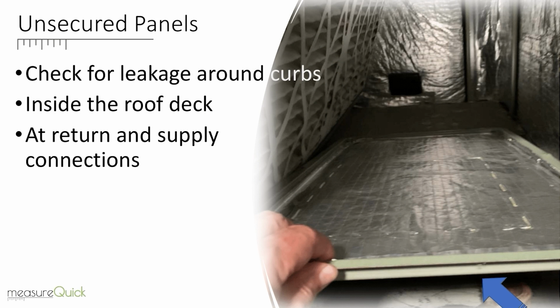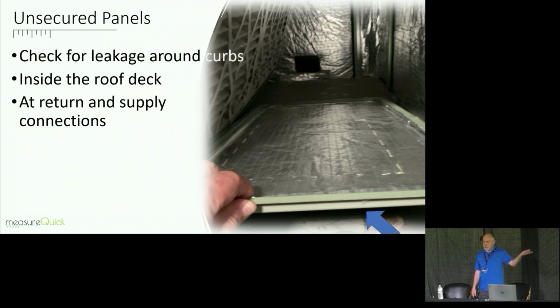Unsecured panels. This is one we ran across. Somebody converted a rooftop unit over from downflow to horizontal. So the guy forgot to screw in the panels on there. And the way I found it was actually an auditory thing, because every time it would come on, I'd hear the panel drop down when it shut off again, right?